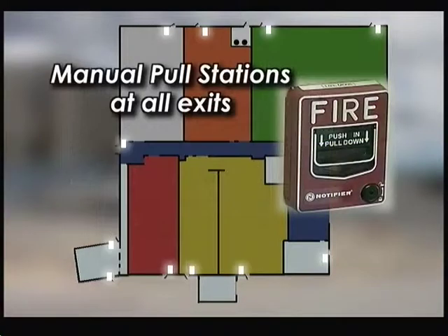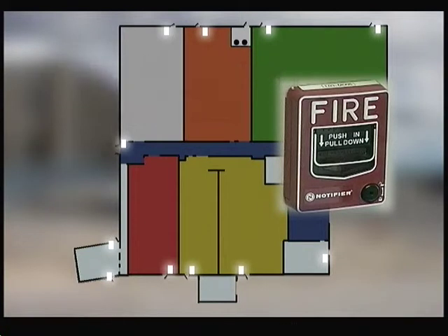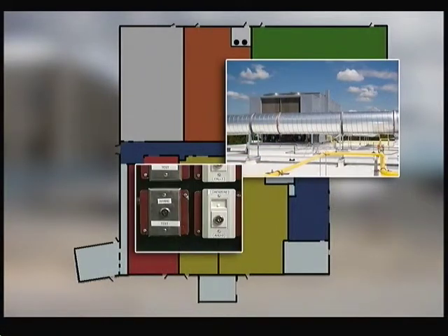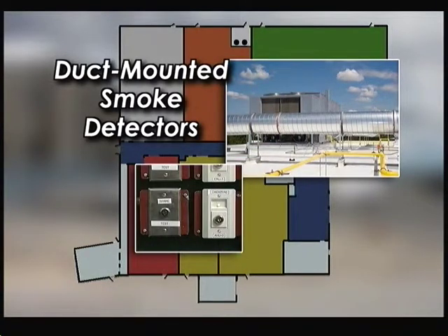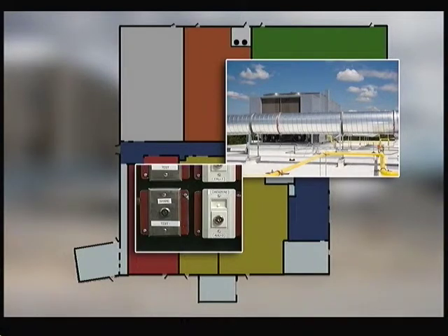The fire alarm system in the building includes manual pull stations at exit discharge locations and top of stair locations, as well as any corridor areas where travel distance to an exit is 200 feet or more. Mechanical system monitoring includes duct-mounted smoke detectors to monitor supply-side ductwork of all HVAC air handlers moving more than 2,000 cubic feet per minute. In some instances, this requires 2 detectors to ensure proper distances downstream from elbows, bends, and other turbulence-causing elements of the ductwork.